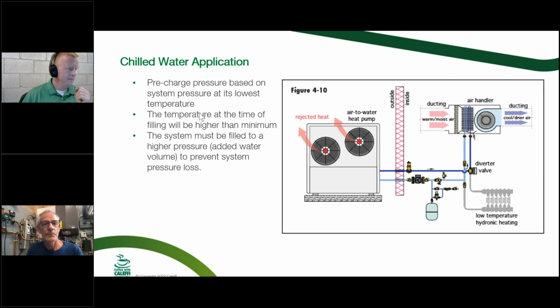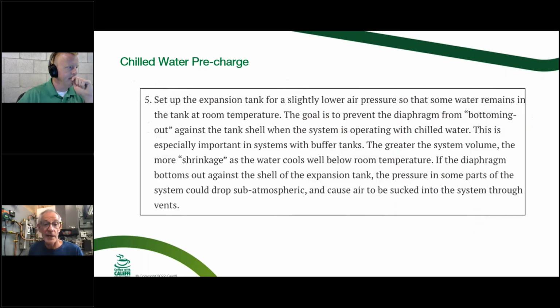So yeah, the time you're filling it, the temperature there, and then what else do I have? It must be filled to a higher pressure. So this is a case where if I'm filling it with, let's say, 70-degree water, and I fire that thing up and I've got a pre-charge and I've got it set at my fill pressure, and I cool that water down, the pressure is going to drop. And the expansion tank, if you had a little bit of fluid in it as you pre-charge it, now you've got a little bit of buffer so we don't see that gauge dropping down to zero. And it can go worse than that in this example here. And maybe I should read this since it is so important. The bottom part is important.